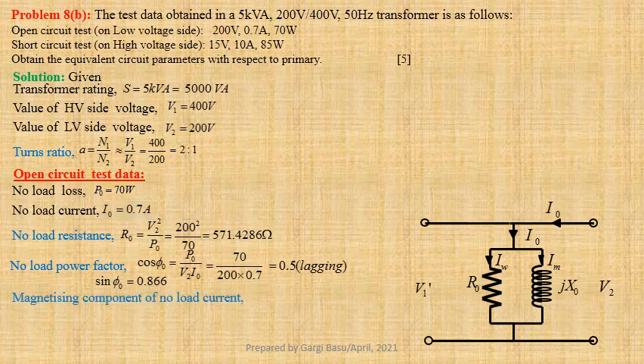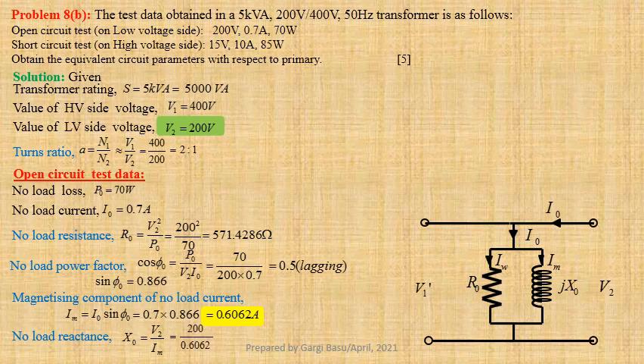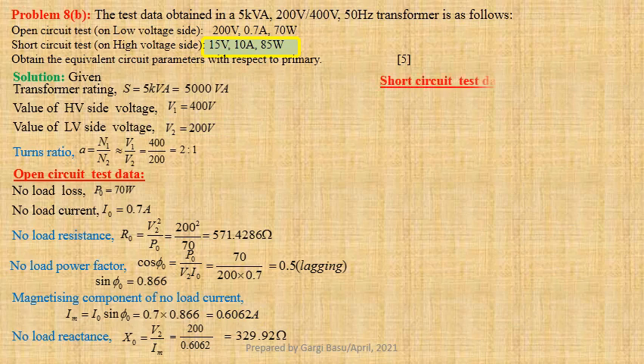Magnetizing component of no load current Im equals I0 sin phi 0. Using values we get 0.7 into 0.866, that gives us 0.6062 ampere. Now we shall determine no load reactance. X0 equals V2 by Im, that is equal to 200 divided by 0.6062, that gives us 329.92 ohm.